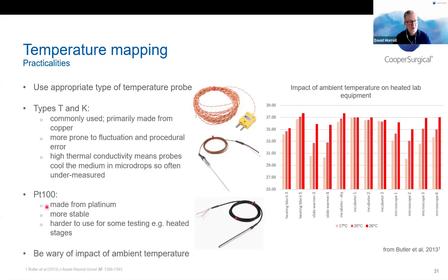A PT100, which is made from platinum, is much more stable, but it's harder to use for some testing such as heated stages. So it's perfect for incubators, where it can sit there and warm up, and it's great. But in a heated stage, you can't put all of this probe onto the heated stage and get a reliable measurement. Just be aware again that however you choose to do it, ambient temperature potentially has an impact.